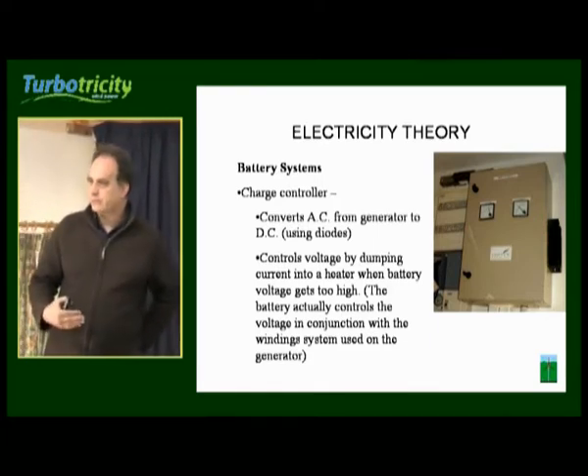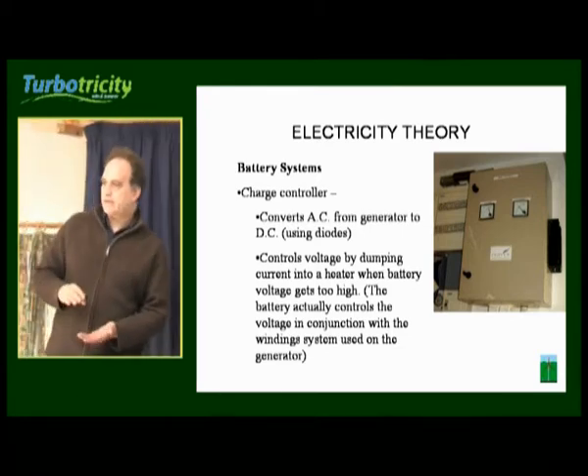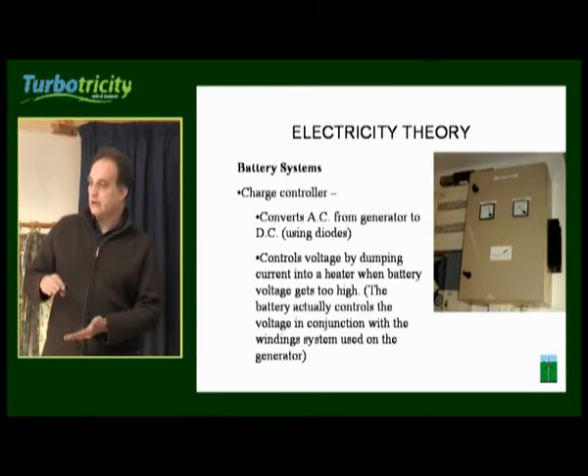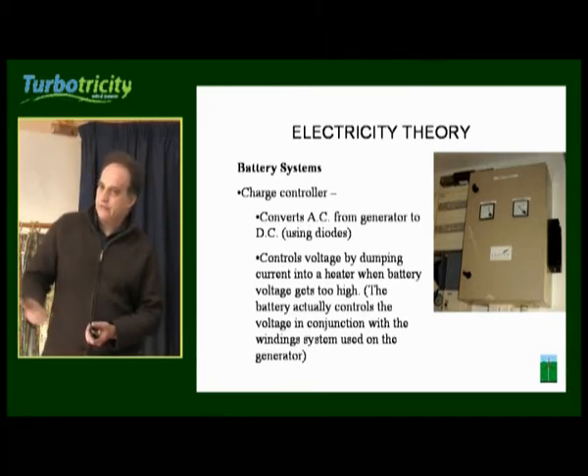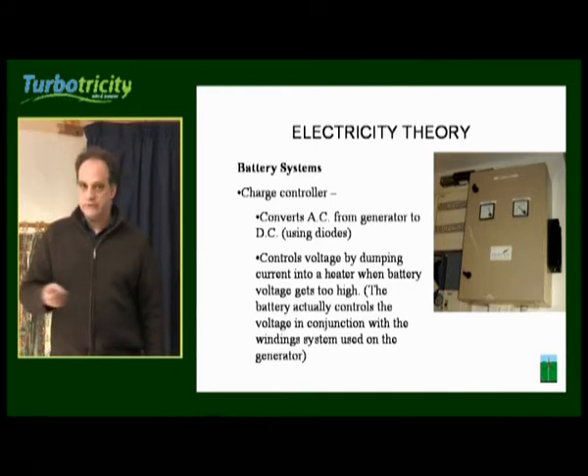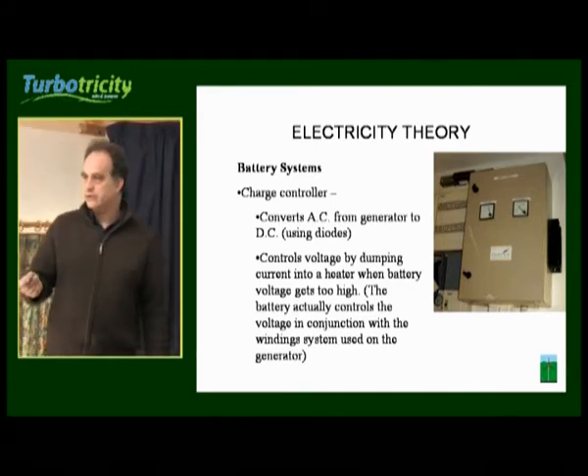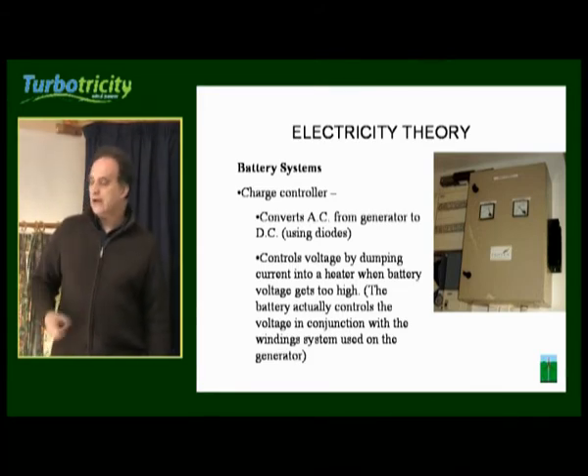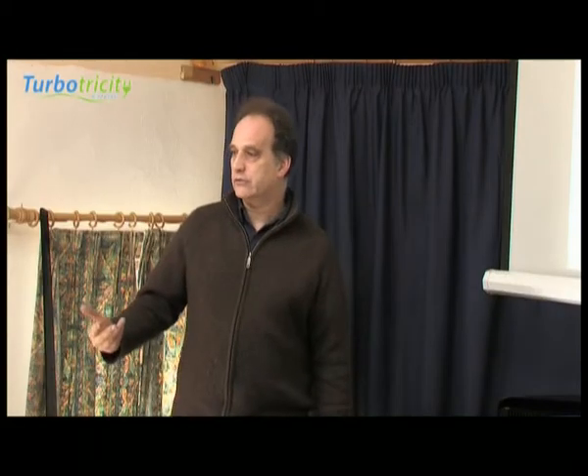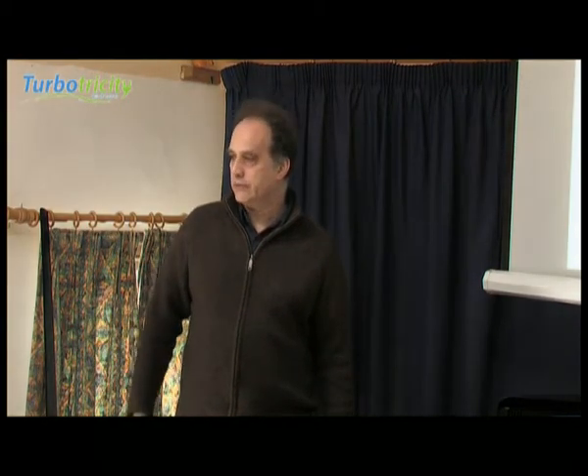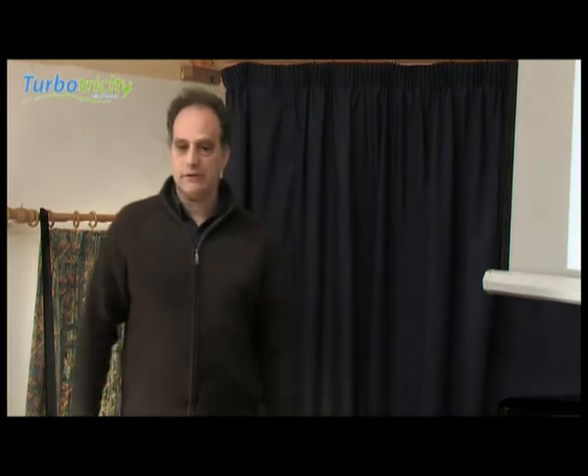The battery will control the voltage up to a point by taking the load, but if the battery voltage goes over a certain limit it means your batteries are either overcharging or are overcharged, and it starts to switch in dump loads. A voltage sensor senses: if the voltage on our 24 volt system goes above 28.5 volts it kicks in a 500 watt load; if it continues above 28.8 volts it kicks in another load, and so on. Ultimately, if it continues to go over-voltage, it throws a resistor into the windings of the motor, stalling the generator and slowing it all down.